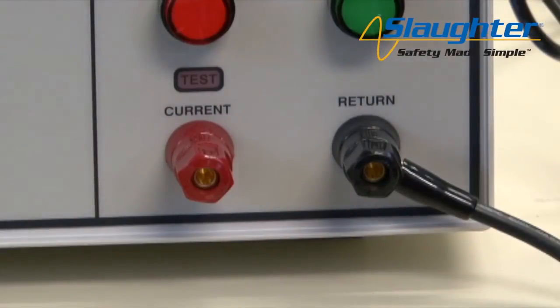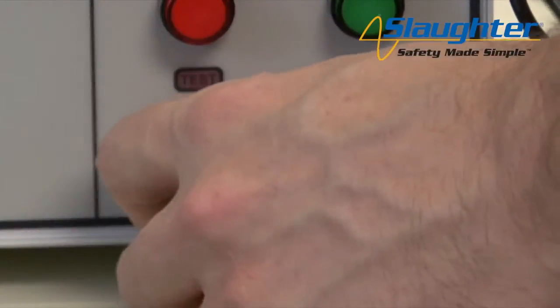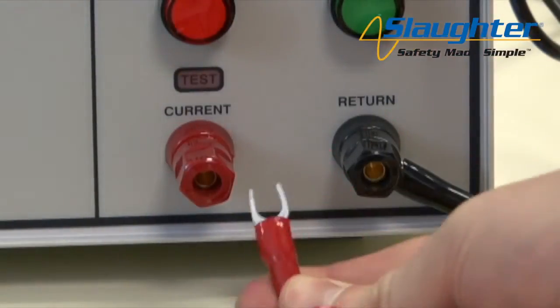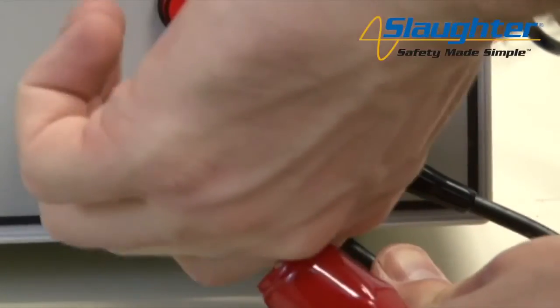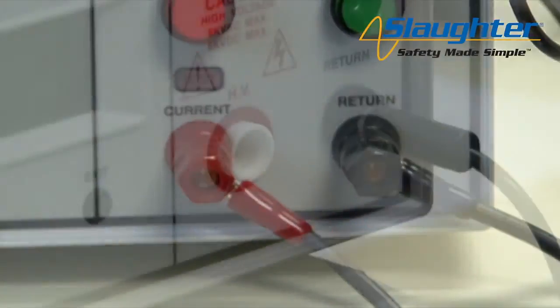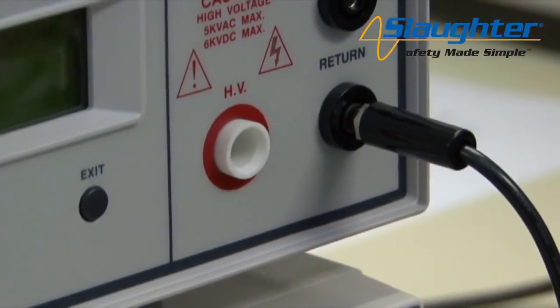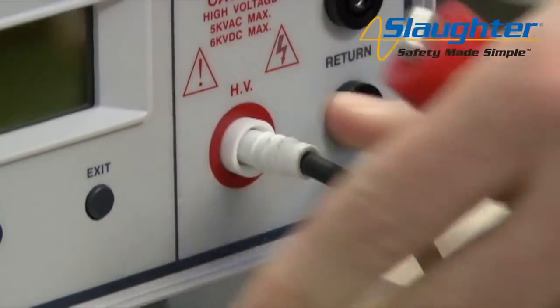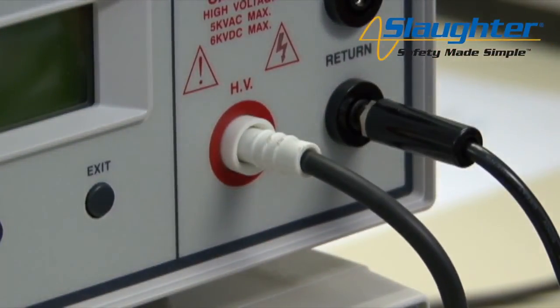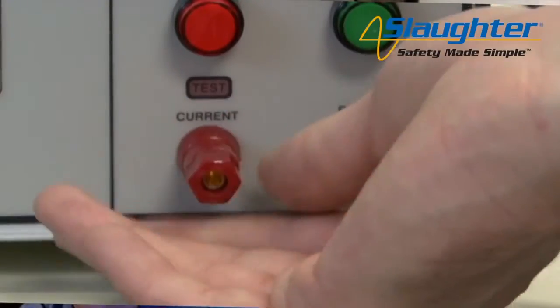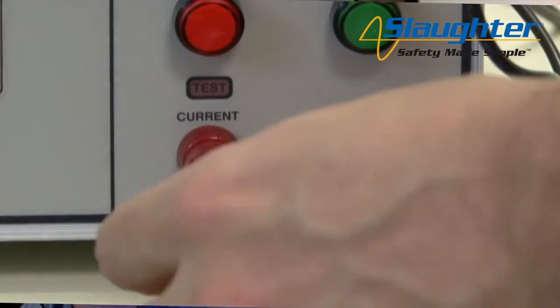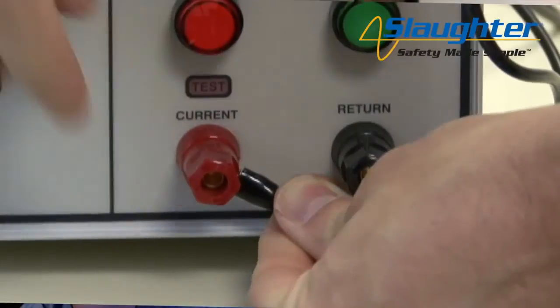Next, connect the red high current lead in the same fashion as the return lead. Unscrew the current terminal and place the high current lead lug over the exposed conductor on the current terminal. Screw the current terminal back in to tighten the connections. Now, connect the high voltage lead by plugging the white Alden style connector into the HV terminal on the 2900 tester. Once all of these connections have been made, you can now connect your DUT. If you are using the optional adapter box, the front panel connections for the current and return are the same. They are simply terminated in the adapter box instead of a clip lead.